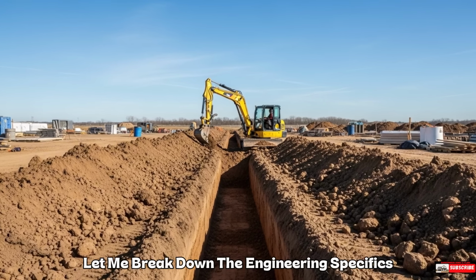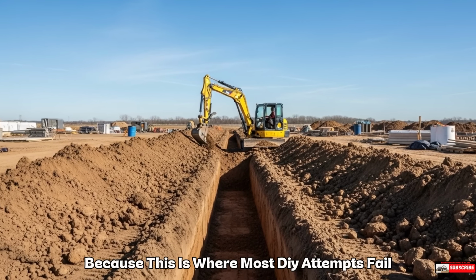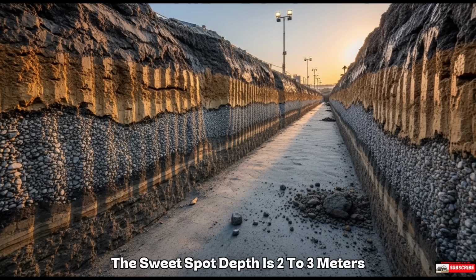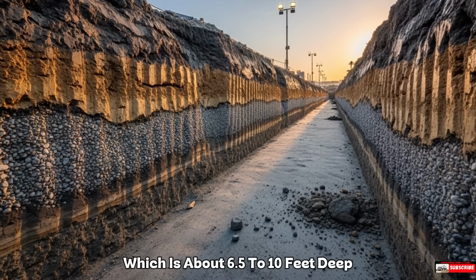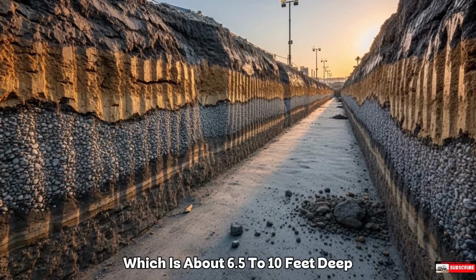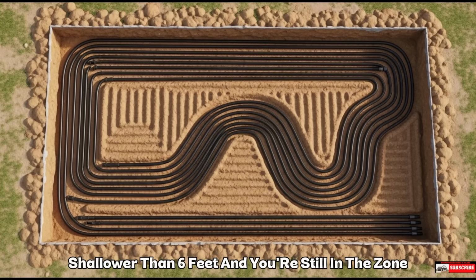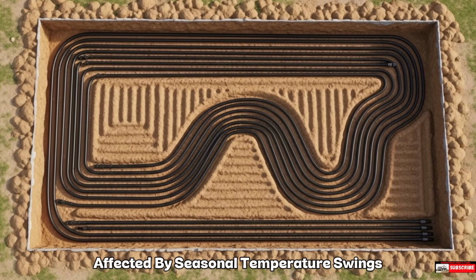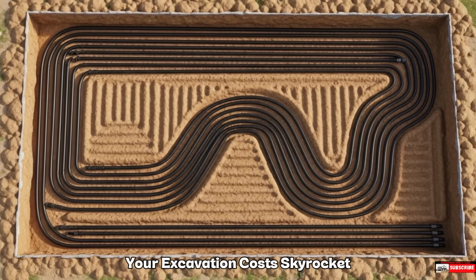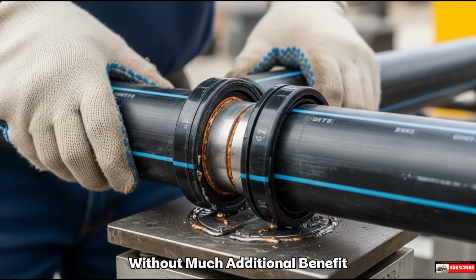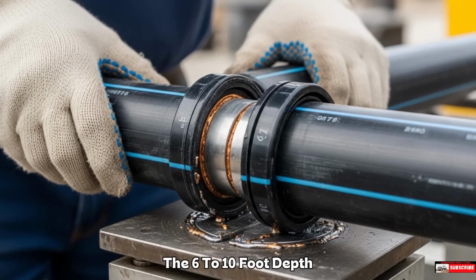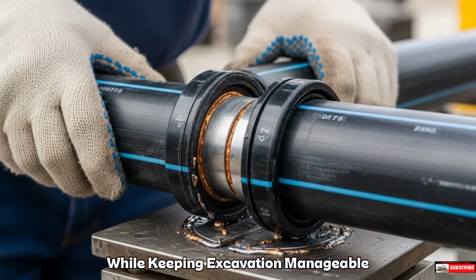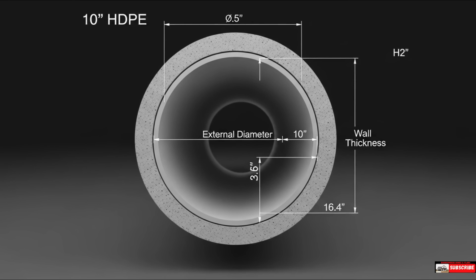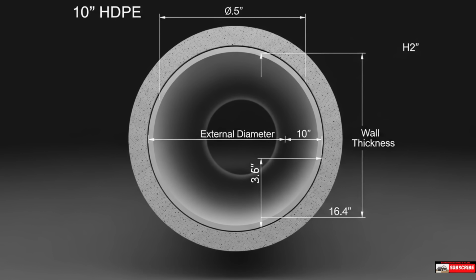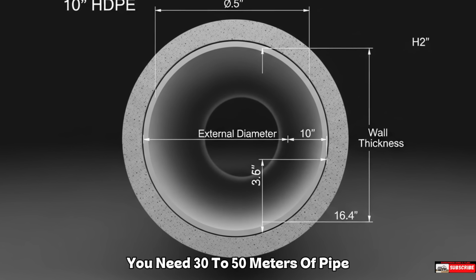Let me break down the engineering specifics because this is where most DIY attempts fail. The sweet spot depth is 2 to 3 meters, which is about 6.5 to 10 feet deep. Shallower than 6 feet, and you're still in the zone affected by seasonal temperature swings. Deeper than 10 feet, and your excavation costs skyrocket without much additional benefit. The 6 to 10 foot depth gives you that stable temperature while keeping excavation manageable. The pipe run length is critical. You need 30 to 50 meters of pipe, which is roughly 100 to 165 feet.